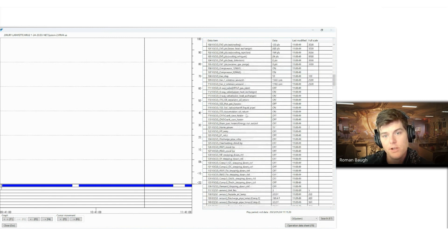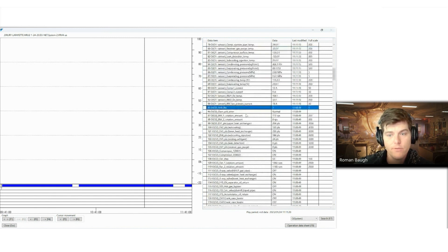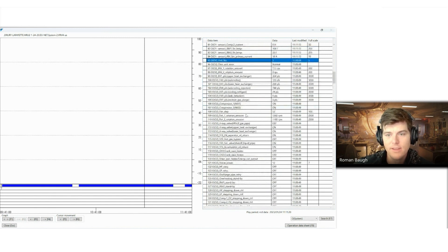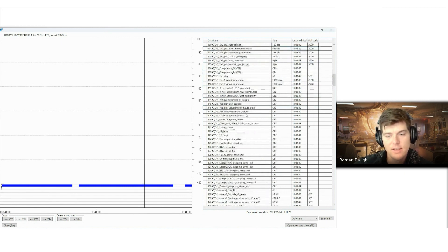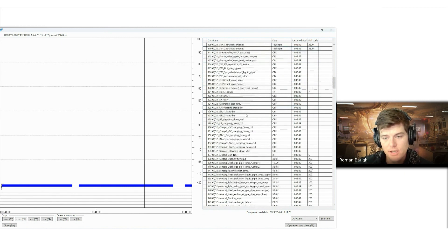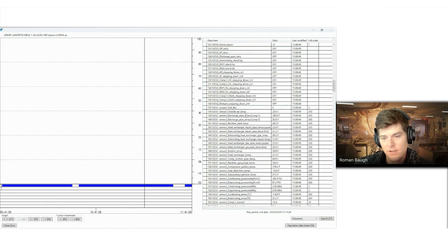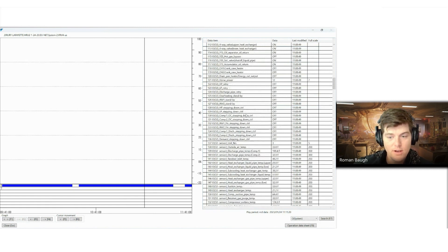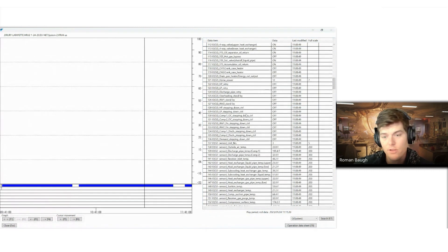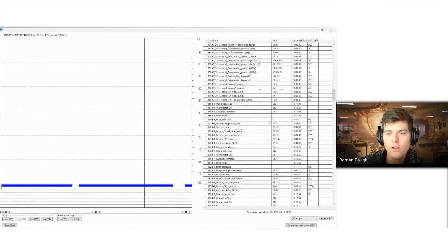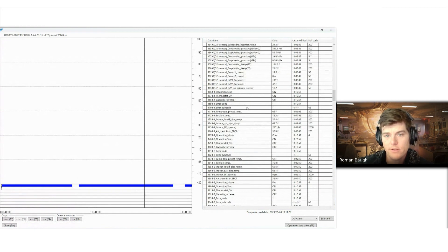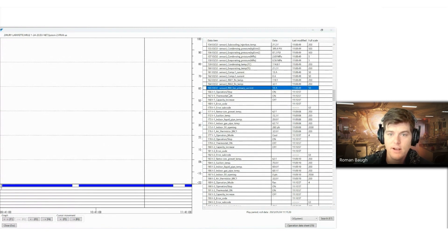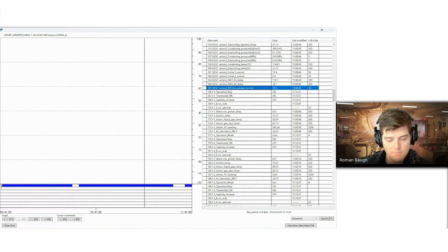So now everything that we just covered is on repeat, but for that specific module. So don't assume that just because you have the repeater data that they are exactly the same because they will modulate differently. They will do things differently. You might find that one unit is in a low pressure step down while the other one is not. All of this information is here for you to reference. Once you get past that, if it's only one module, you only have the OU1.